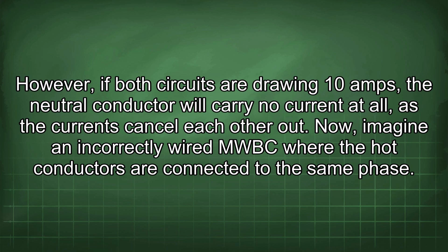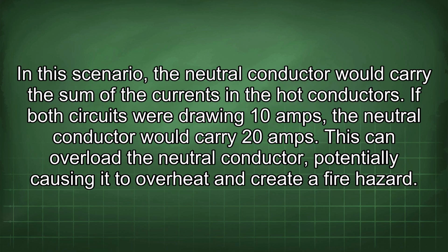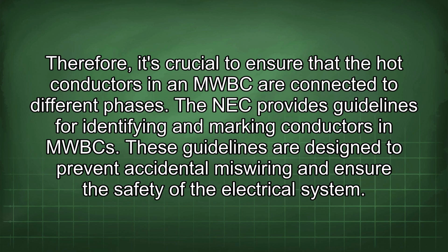Now, imagine an incorrectly wired MWBC where the hot conductors are connected to the same phase. In this scenario, the neutral conductor would carry the sum of the currents in the hot conductors. If both circuits were drawing 10 amps, the neutral conductor would carry 20 amps. This can overload the neutral conductor, potentially causing it to overheat and create a fire hazard. Therefore, it's crucial to ensure that the hot conductors in an MWBC are connected to different phases.